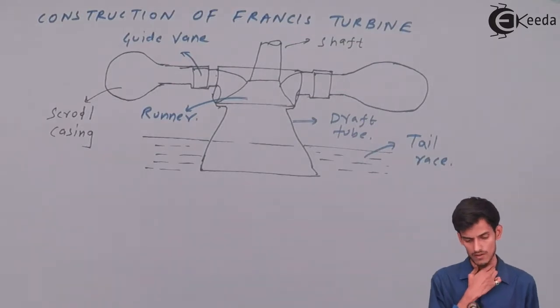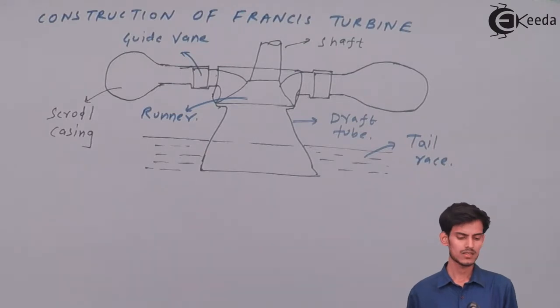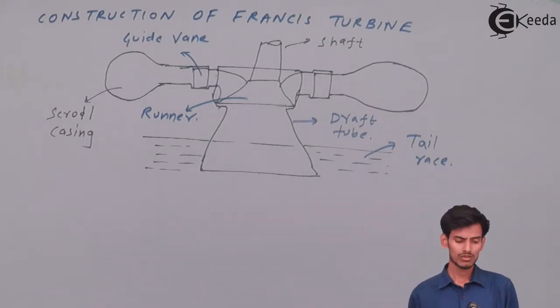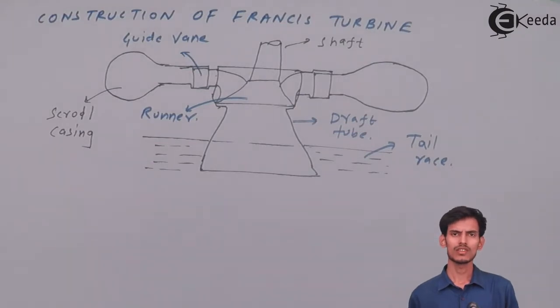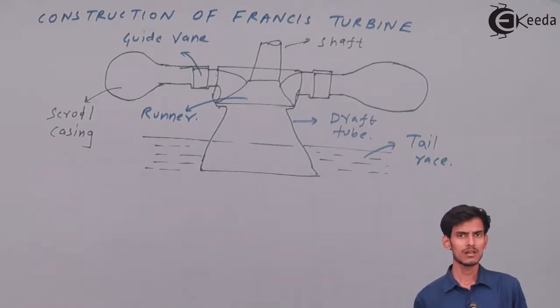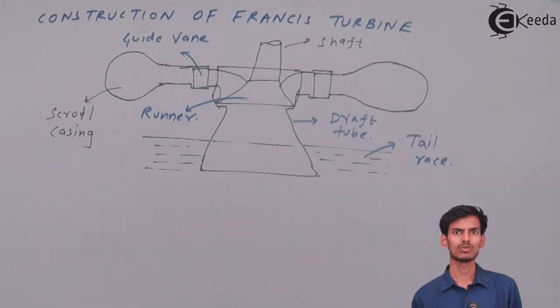As you can see in the front view, there is a scroll casing, then a part called guide vanes, then a runner, then something called a draft tube, and finally the tail race. As water enters the scroll casing from the penstock, it goes around the circumference and into the guide vanes. The guide vanes are made of an aerofoil shape so water passes through without friction, enters at a particular angle, and strikes the runner blades without any shock.